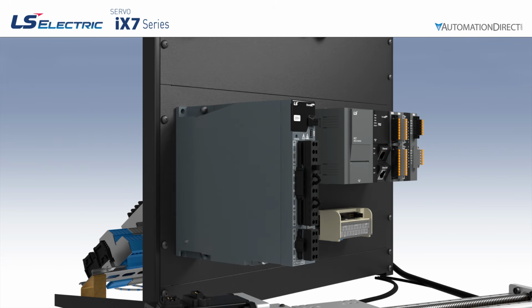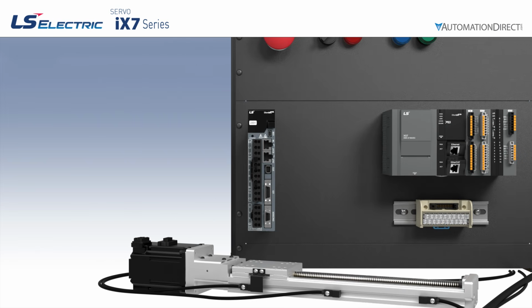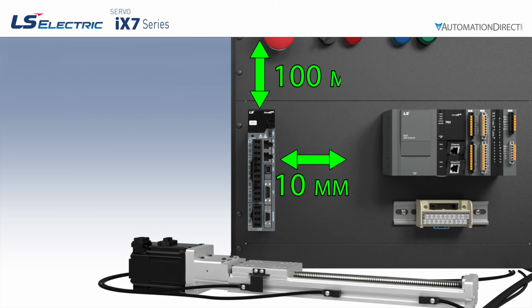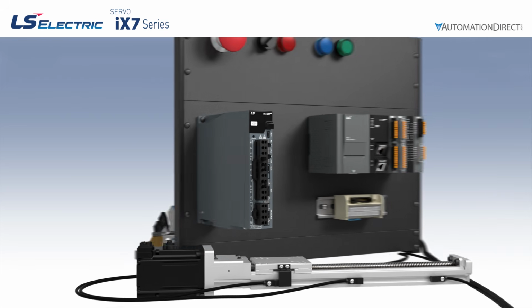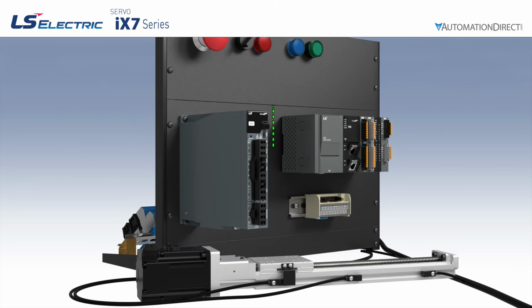It mounts directly onto a control panel. For proper cooling and accessibility, give it at least 10 millimeters of clearance on each side and 100 millimeters above and below. There's no specific front clearance requirement, but make sure you have room for cables and wiring and can see the drive display for status information.